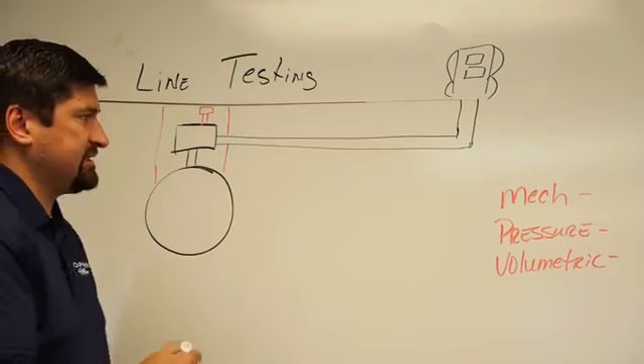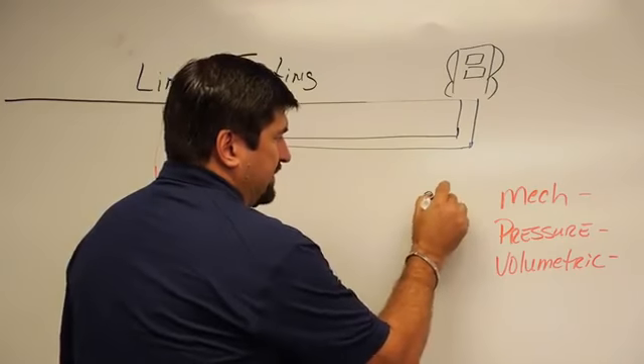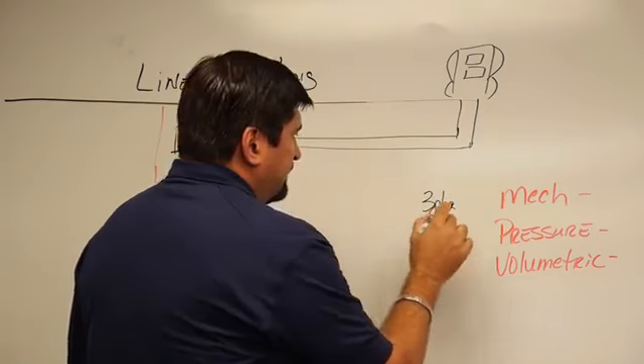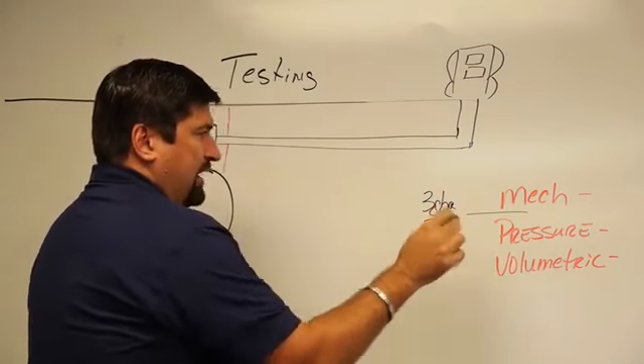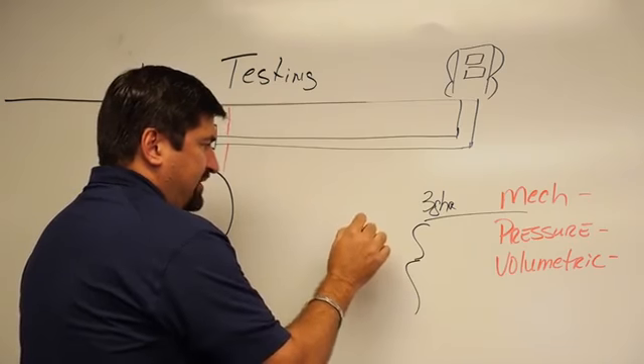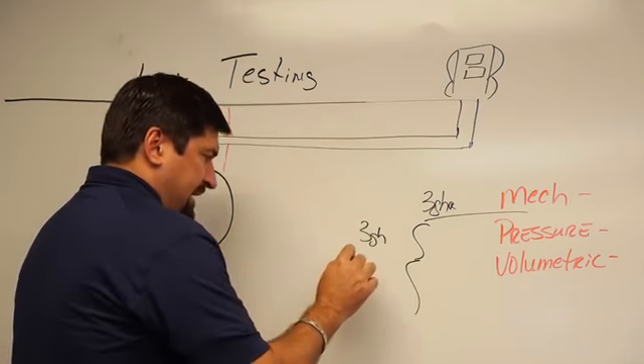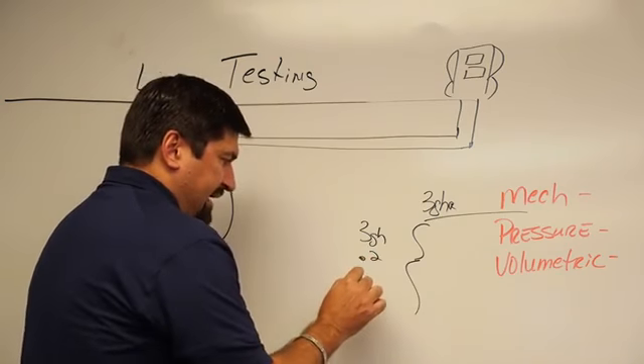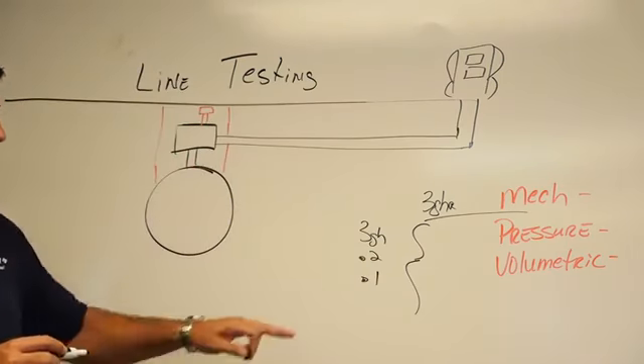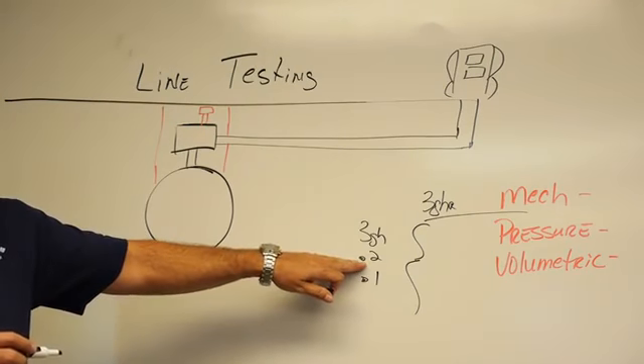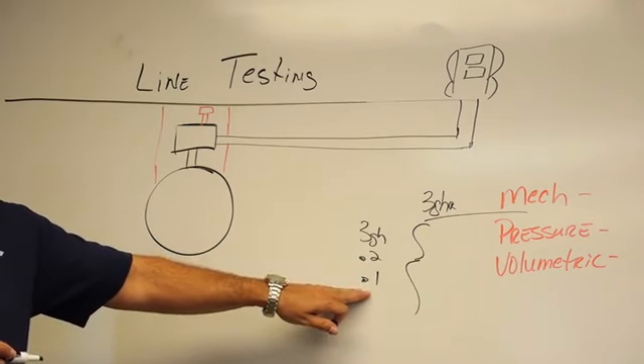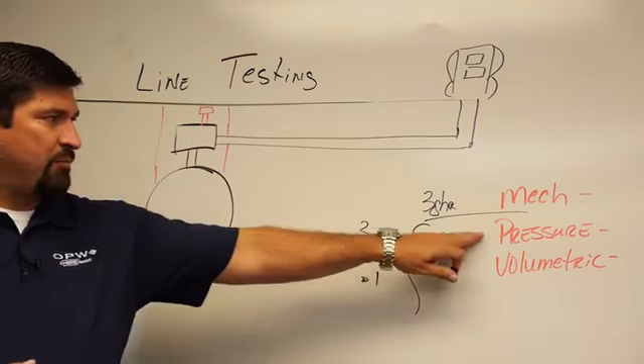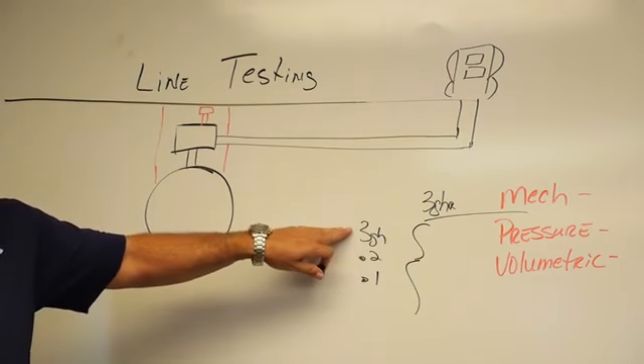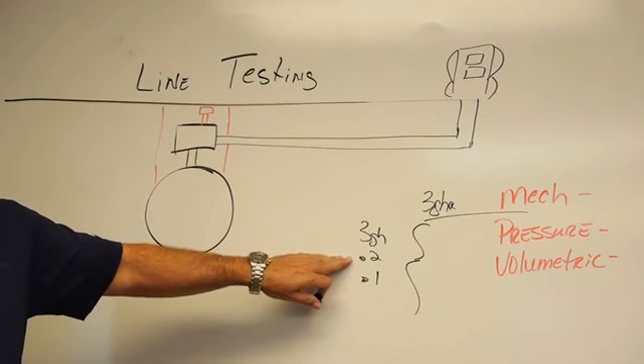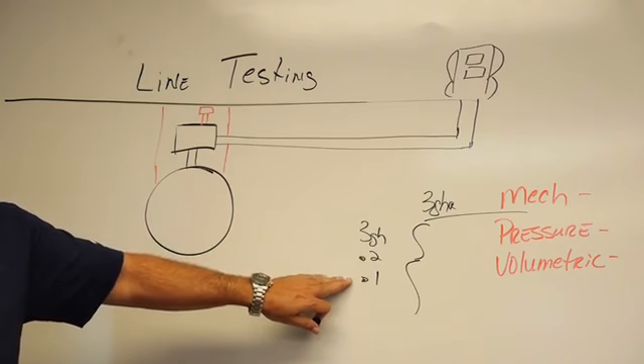Now, when I start looking at these, mechanical will give you a 3 gallon per hour line leak test. When I look at pressure or volumetric, these have to do a 3 gallon per hour. They have to be able to run a 0.2 monthly, and they have to have the capability of running a 0.1 annually. But if I run a 0.2 line test every month, I can suspend my 0.1 for up to 5 years, depending on state and local requirements. Some are 3, some are 5, but most pressurized or volumetric line tests will run the 3 gallon after every dispense, and then they'll try to run at least a 0.2 a month and a 0.1 every year.